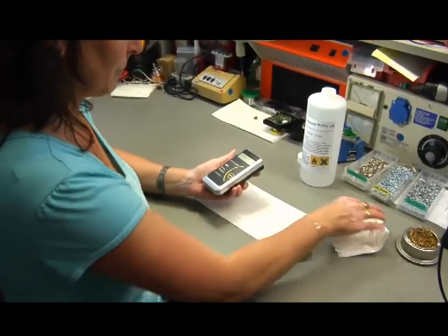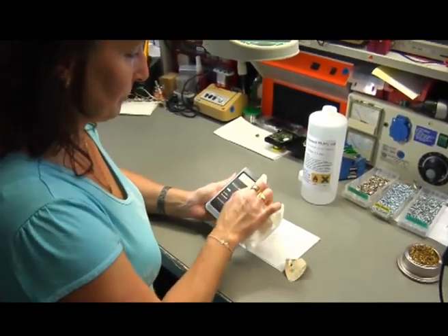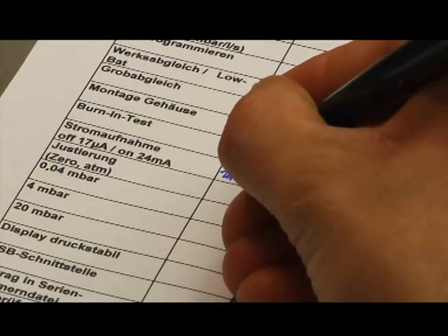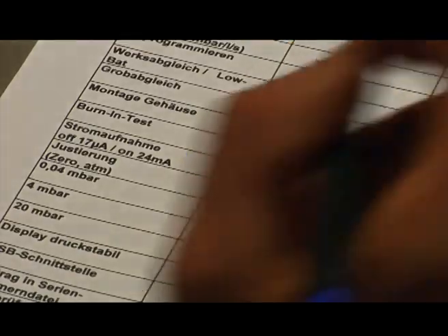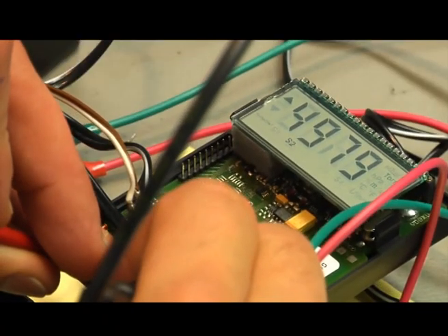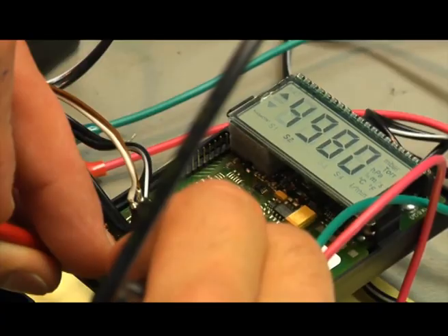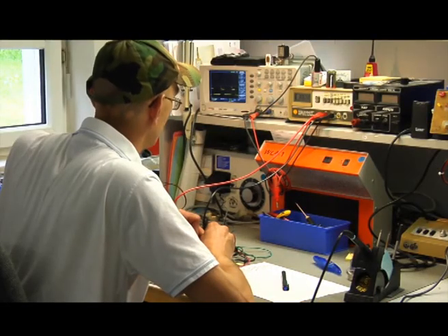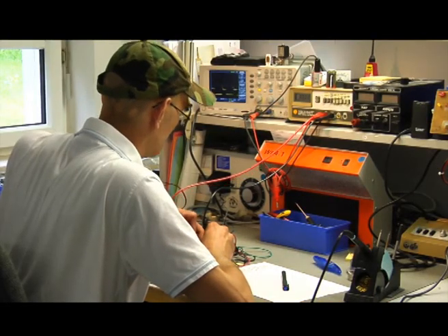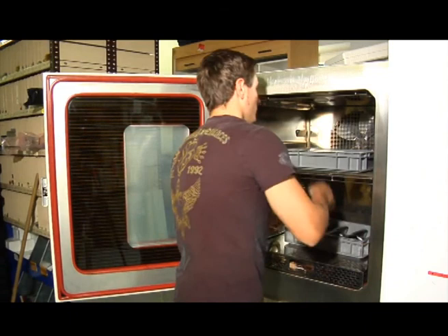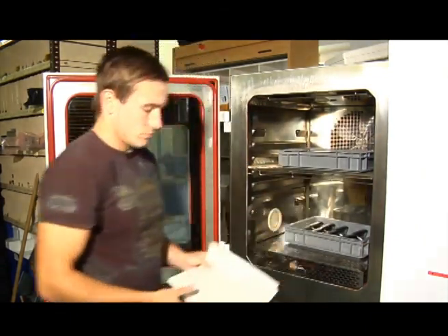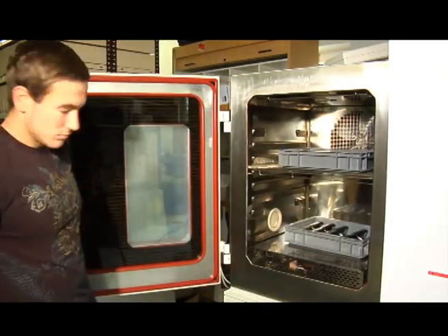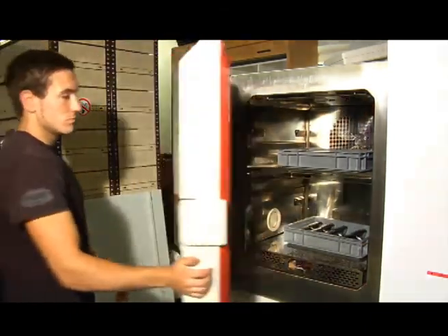Only through constant tests and the strict use of traceable inspection sheets can the high product quality be maintained permanently. On top, every sensor is put through a 24-hour burn-in test with temperature changes from minus 10 degrees Celsius to plus 50 degrees Celsius in hourly intervals.